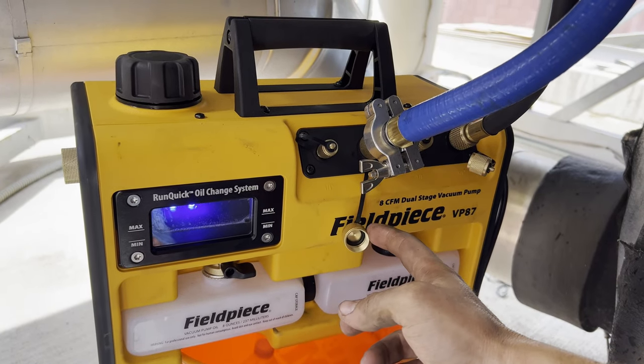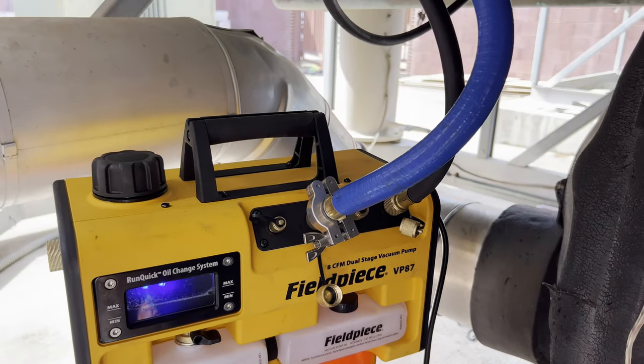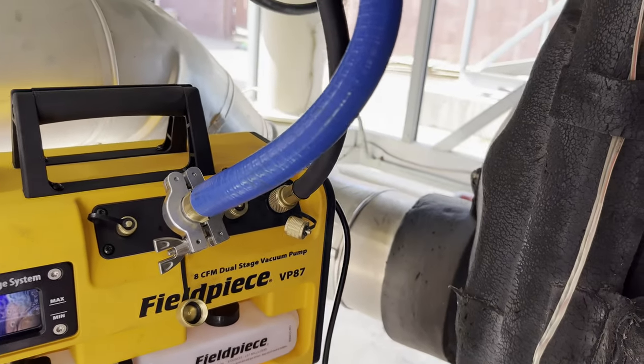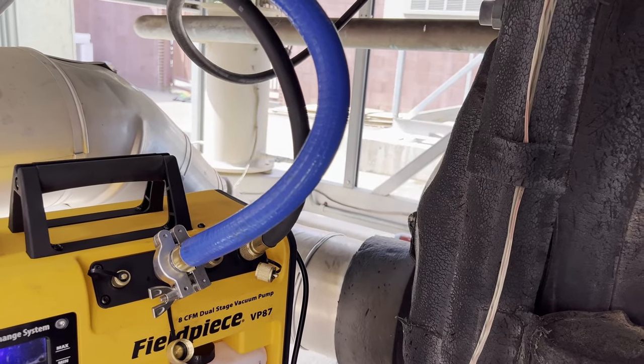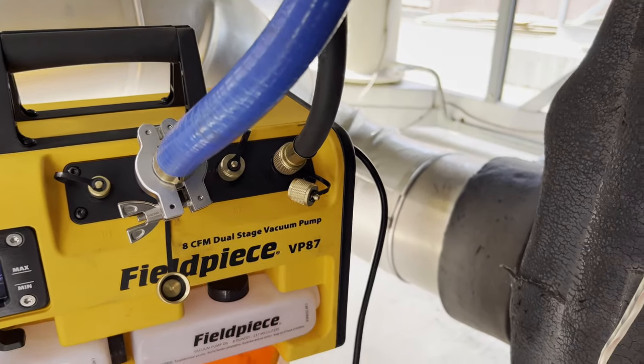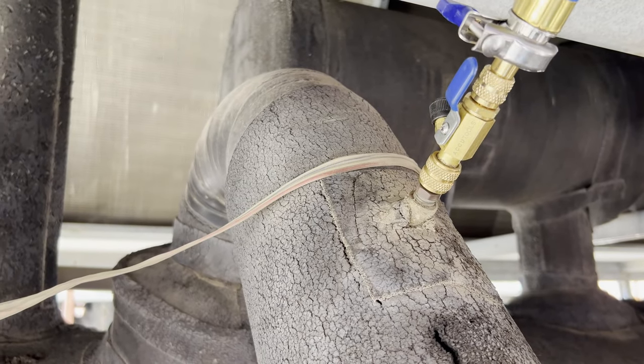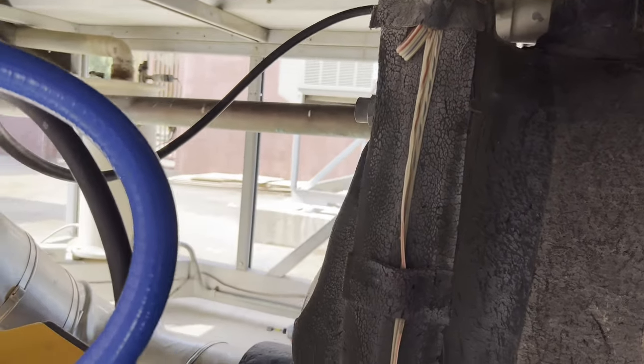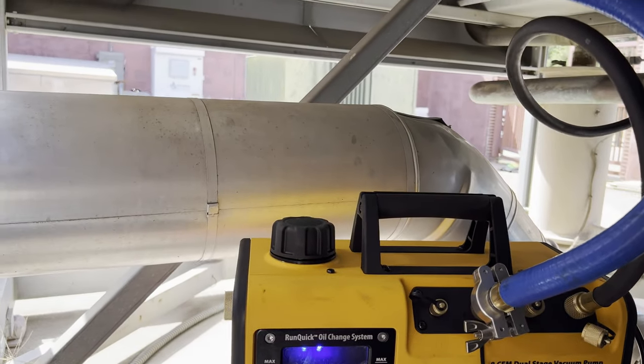I'm going to give you all a little rundown on the Fieldpiece 8 CFM VP87 Vacuum Pump and how to use it. First you're going to set up your connections. I'm using a direct method, going straight from the vacuum pump to core removal tools on the suction and liquid line. We'll start off with these closed and the pump powered off.